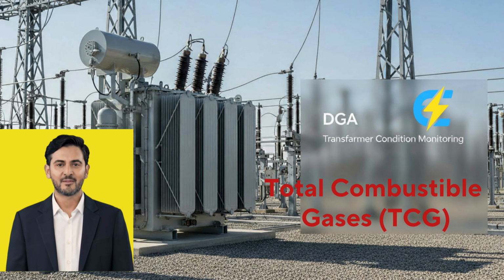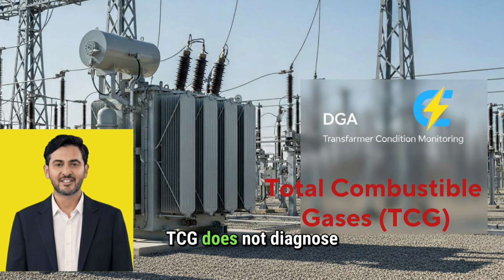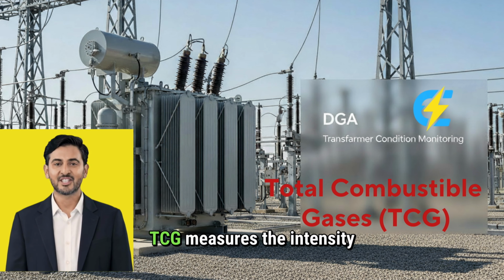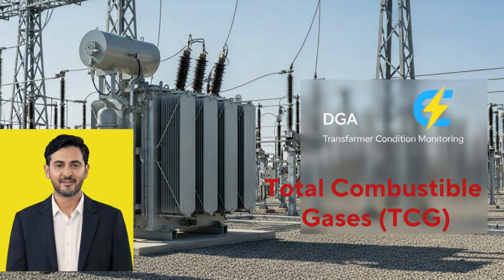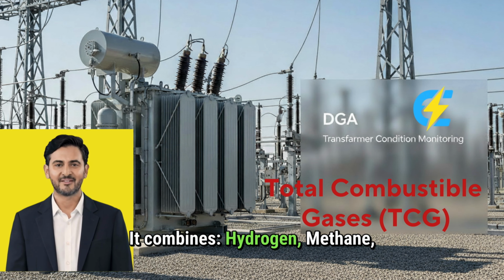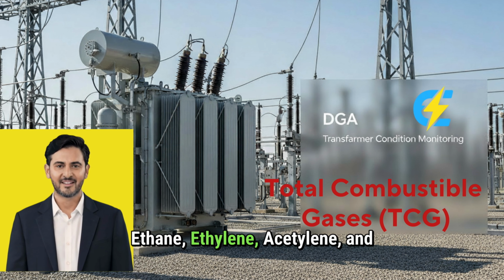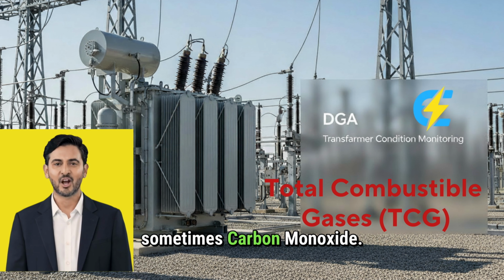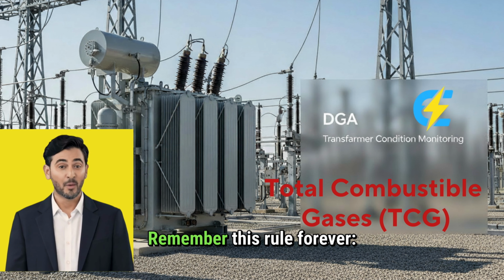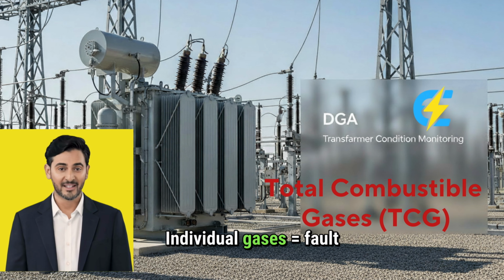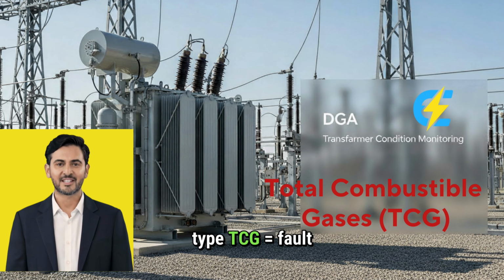So friends, this is the real meaning of TCG in DGA. TCG does not diagnose a fault. TCG measures the intensity of fault activity. It combines hydrogen, methane, ethane, ethylene, acetylene, and sometimes carbon monoxide. Remember this rule forever. Individual gases: fault type. TCG: fault severity.